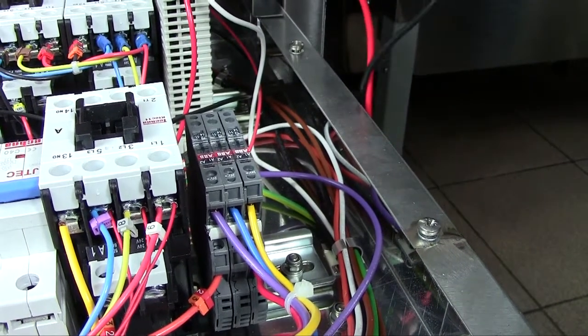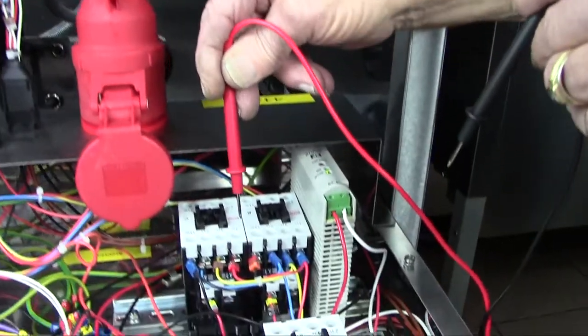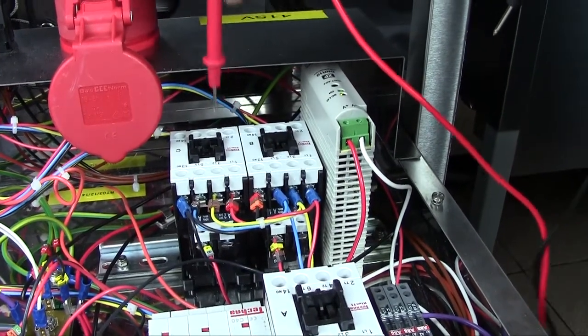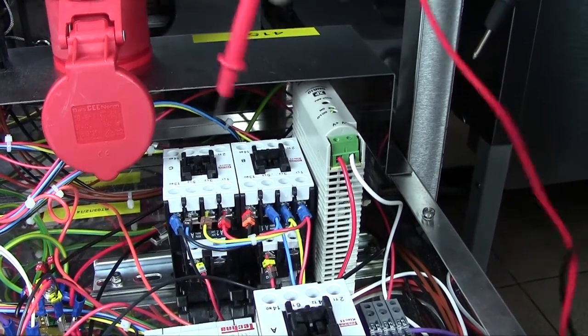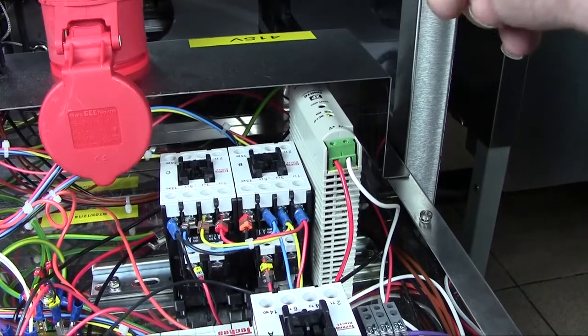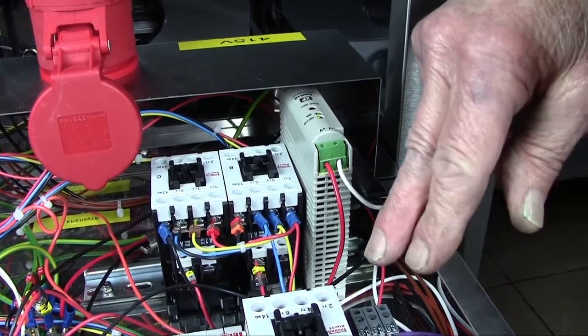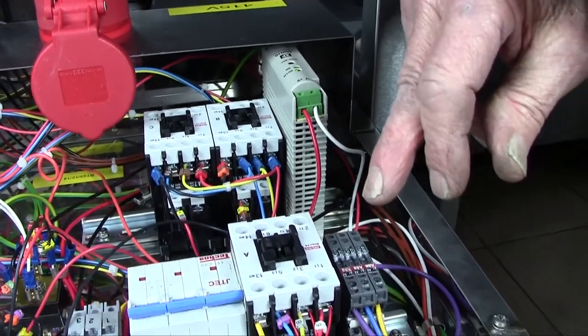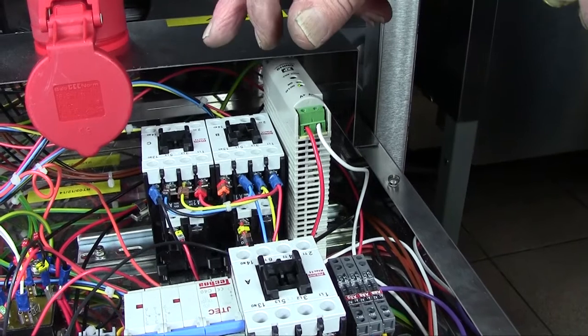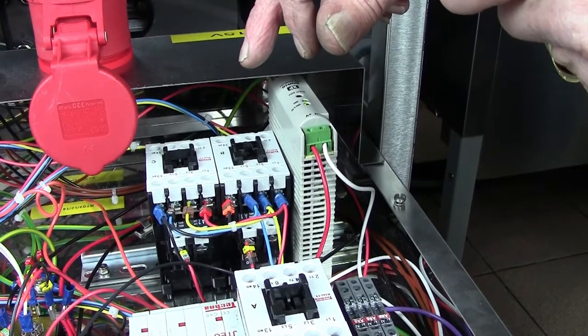The next check is to check whether the actual contactor is working from one side to the other as regards voltage flowing through it. It could have burnt contacts. If it has, replace it. And going back to the beginning, if the relay is not showing voltage, replace it. If the contactor is not pulling in, replace it. With relay and contactor opening and closing, check the contactor for continuity. If the control board is sending a continual current and the relay is actuating and the contactor is actuating and this goes on, replace the control board.